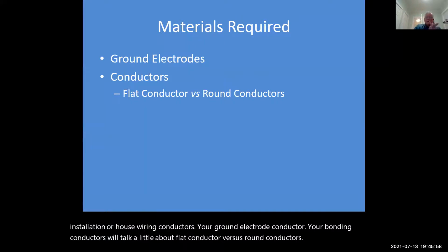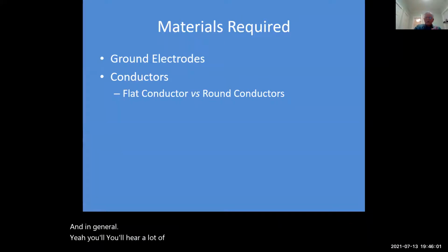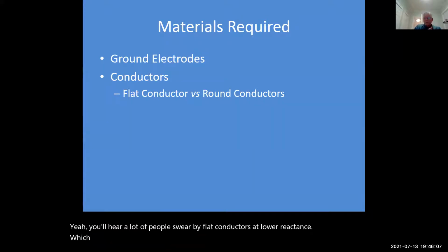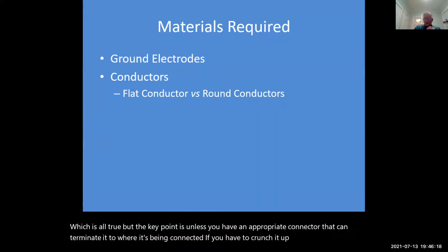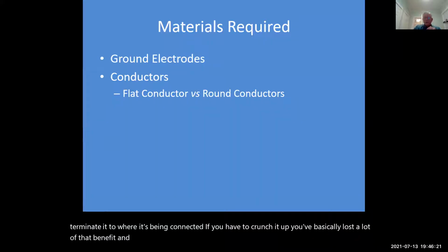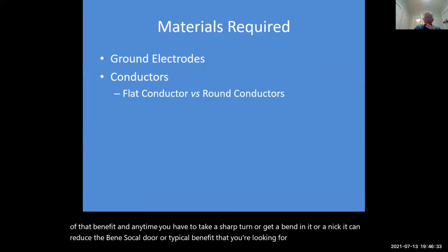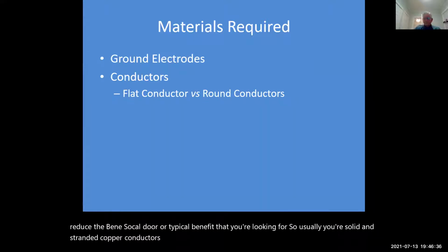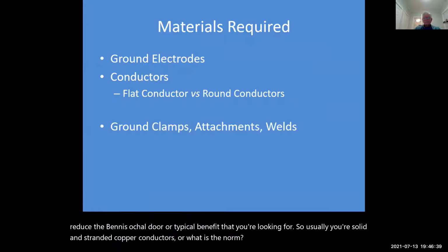In general, you'll hear a lot of people swear by flat conductors for lower reactance, which is all true. But the key point is, unless you have an appropriate connector that can terminate it to where it's being connected, if you have to crunch it up, you've basically lost a lot of that benefit. And anytime you have to take a sharp turn or get a bend in it or a nick, it can reduce the typical benefit that you're looking for. So usually solid and stranded copper conductors are the norm.